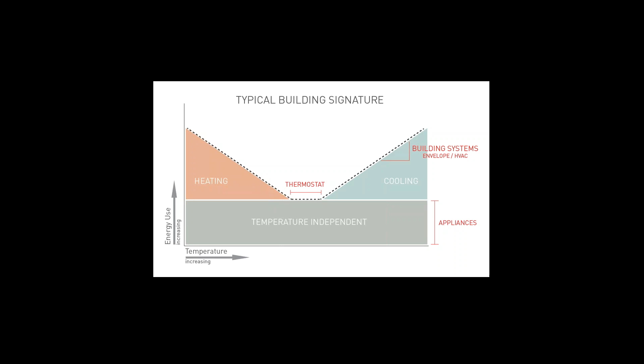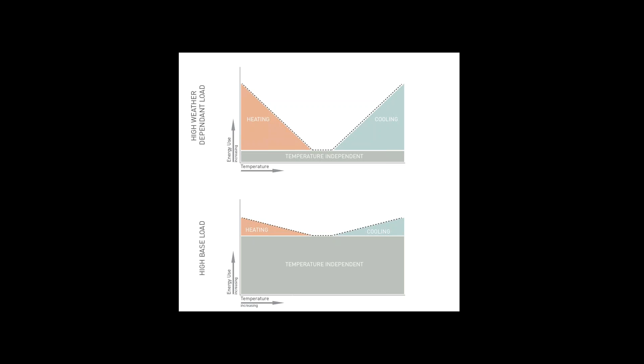Some projects might have a very low temperature-independent base load but very high heating and cooling loads, which would indicate an inefficient project without many appliances. Or you might have a project like Hogpen, where there are a lot of plug loads, the pool, security, but a very efficient HVAC system, so very little additional load for heating and cooling. This really helps us not just diagnose existing buildings, but also predict where we need to focus our efforts.